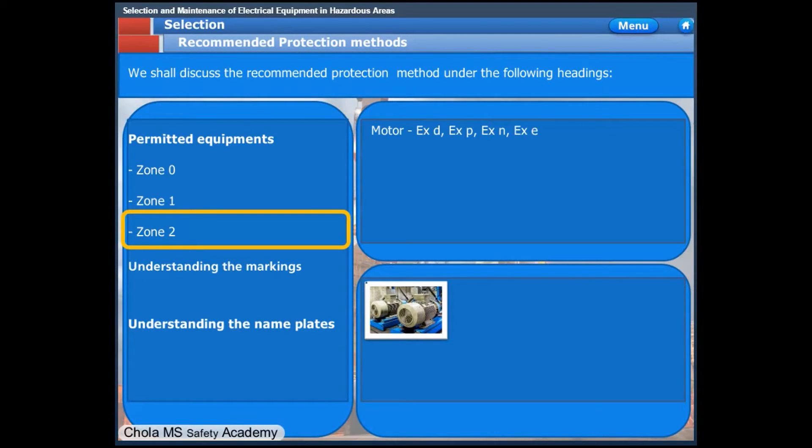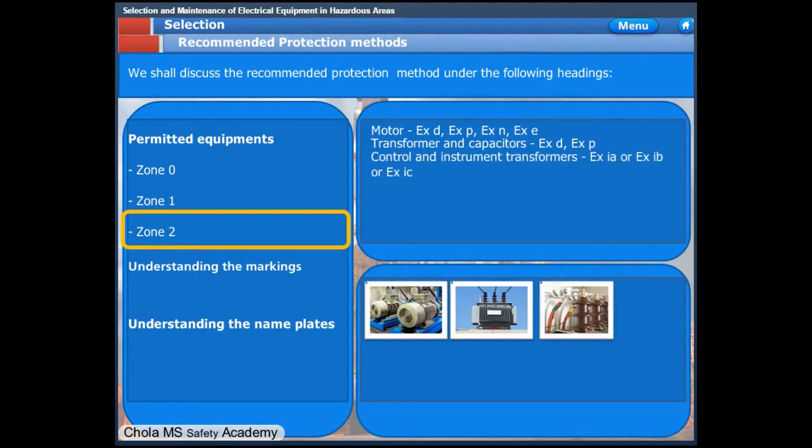However, Zone 2 apparatus cannot be used in Zone 1 areas. Transformers and capacitors may be flame-proof type or pressurized enclosure type. Control and instrumentation transformers shall intrinsically be safe type, complying with Ex ia, Ex ib, or Ex ic. Ex ic is designed for Zone 2 areas and is not suitable for Zone 1 areas.